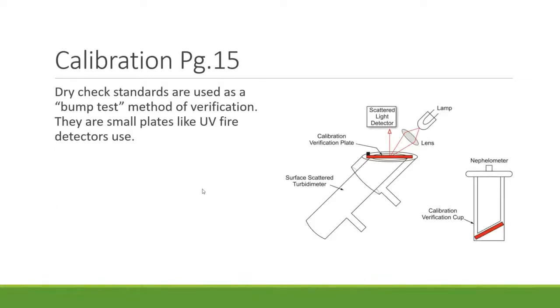There are also dry check standards — a bump test or reference verification method. These are similar to the small plates used for UV fire detection, where plates of different darkness or filtering represent different concentrations. You hold them in front of the sensor to represent a specific concentration for whichever unit your device uses.